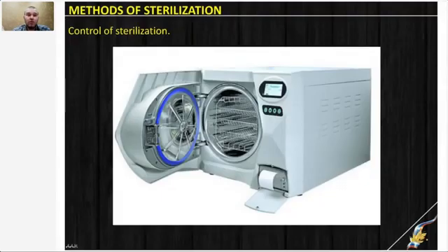And of course, nowadays, I will turn back to the picture. I already showed you that autoclave, but please take a look at the right lower corner of the device. We can see that it is a paper check printed here, and it's looking like a simple bill. It is a paper where all parameters of sterilization are shown, and the device can monitor. Modern devices of course have built-in computers, they have multiple detectors, they can print your complete graph of sterilization, in which time point which temperature was detected by the device.